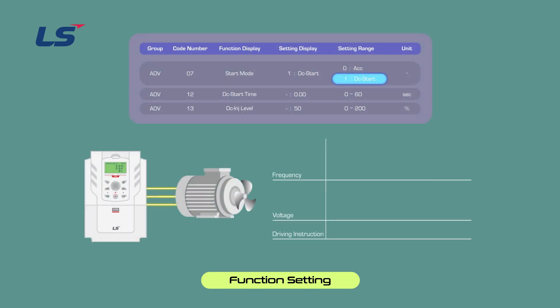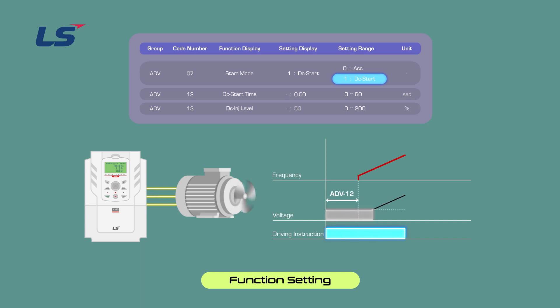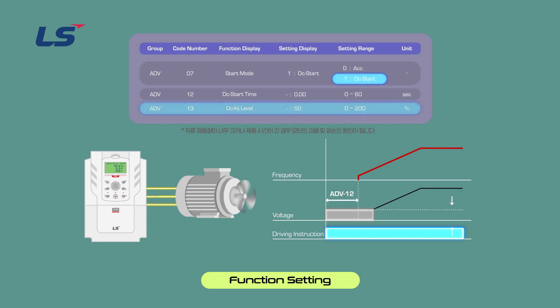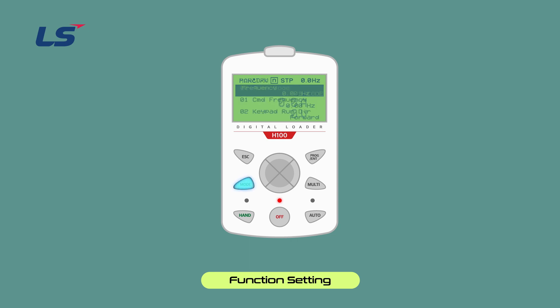The DC starting method applies DC voltage to the motor for the set DC start time and then accelerates. If the motor is rotating before voltage is output from the AC drive, DC braking will stop the motor rotation and then accelerate. It can be used in vertical loads using mechanical brakes on the motor shaft when constant torque is required even after opening the mechanical brakes. The DC braking amount of DC injection level can be set based on the motor rated current and must be set to a value within the AC drive rated current. Select 1 DC start in ADV7 start mode.